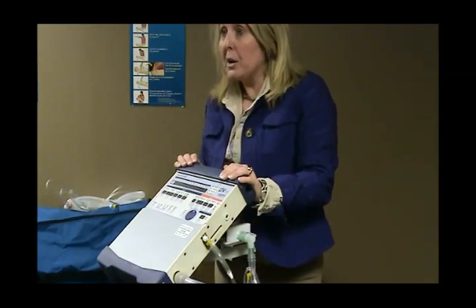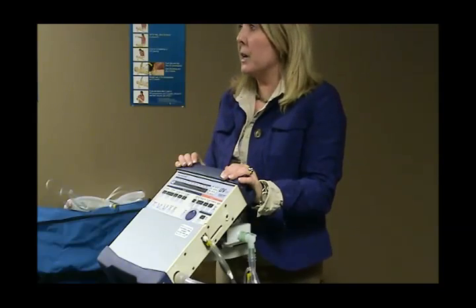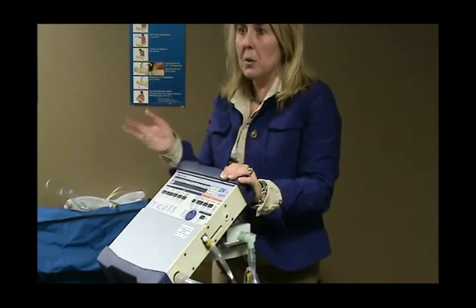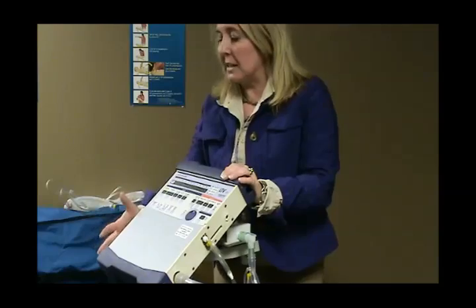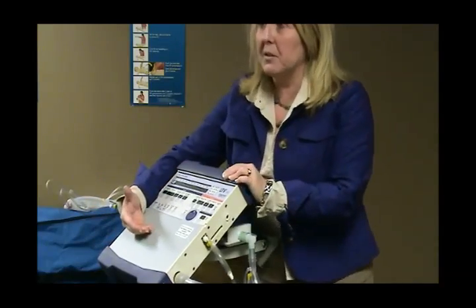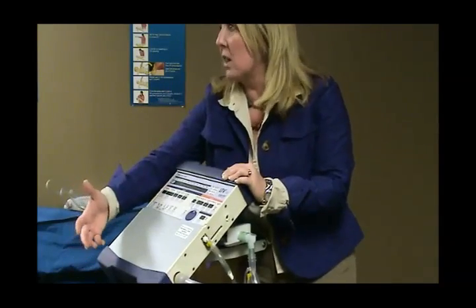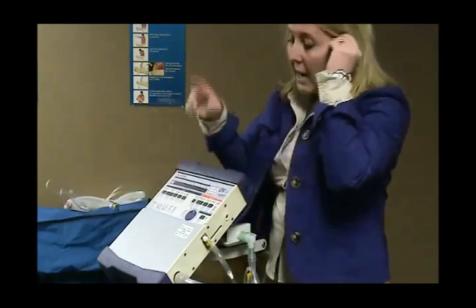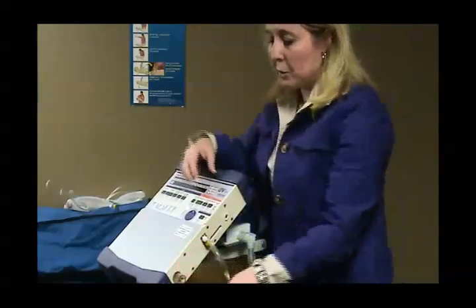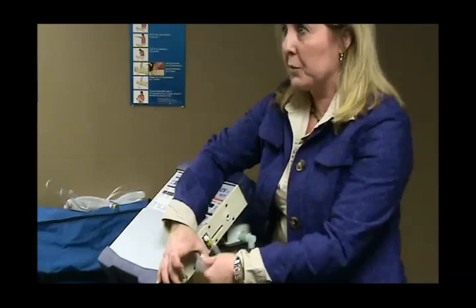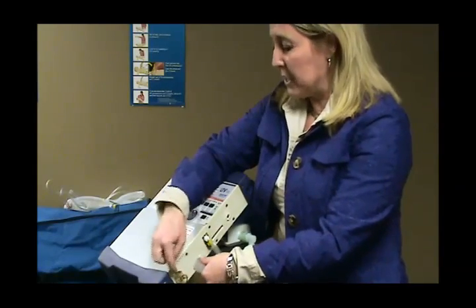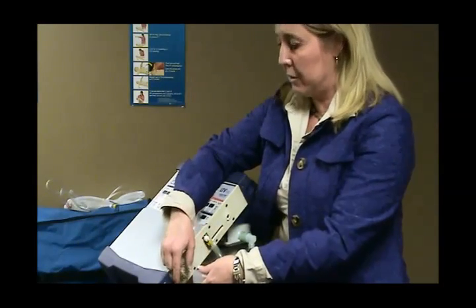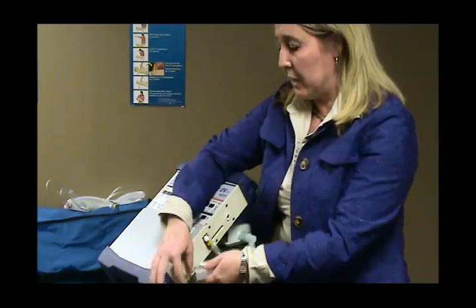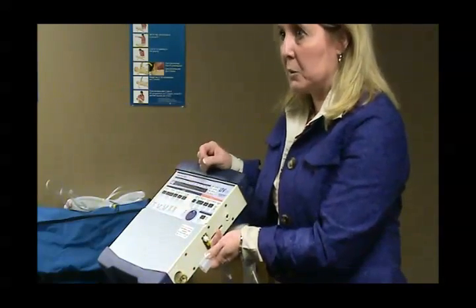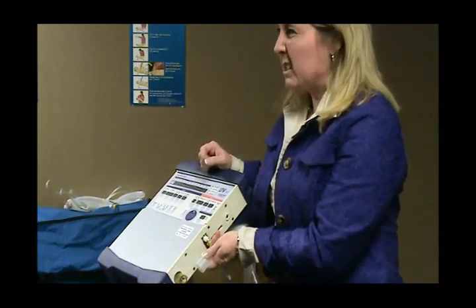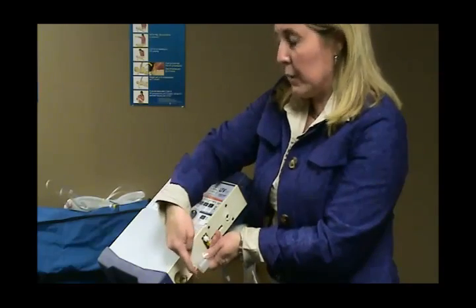There is a flow that goes through the ventilator all the time, that bias flow that I talked about, 10 liters per minute going through the vent all the time. So you will not see anything build up in the ventilator unless it's heavy enough that it can fall out through 10 liters of flow. I say that because every once in a while, first of all, you will usually have a microbacteria filter off of this side of the vent. If it's a nuisance by the way you have it set up on the chair or something, with a filter sticking out of there, you can get an elbow and reroute it this way, okay? Just ask the equipment company for a 90-degree elbow to go on there.